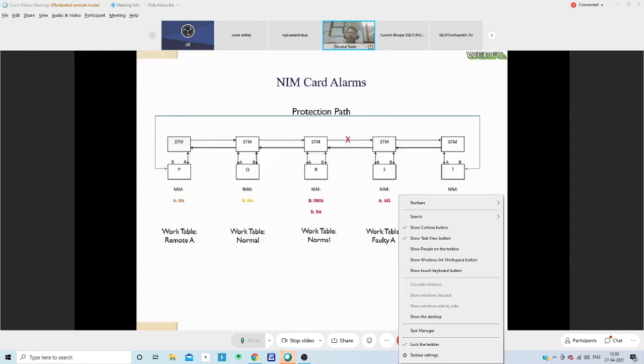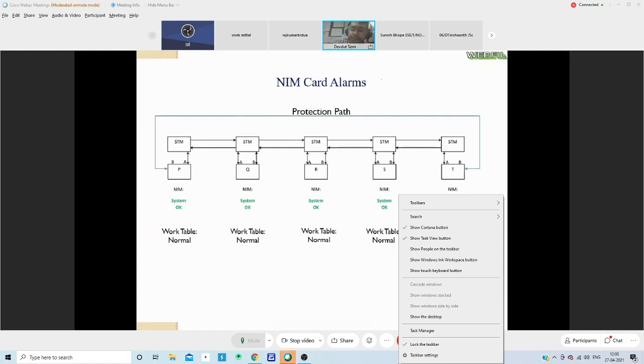So basically, what you need to remember is that the table the MUX is working on at the moment depends on what alarms are in the NIM card of that MUX. In case of AIS, RXF, or LOS, the MUX will automatically switch to the corresponding faulty table. And in case of remote A or remote B, if remote table switching is enabled, the MUX will automatically switch to the corresponding remote table.